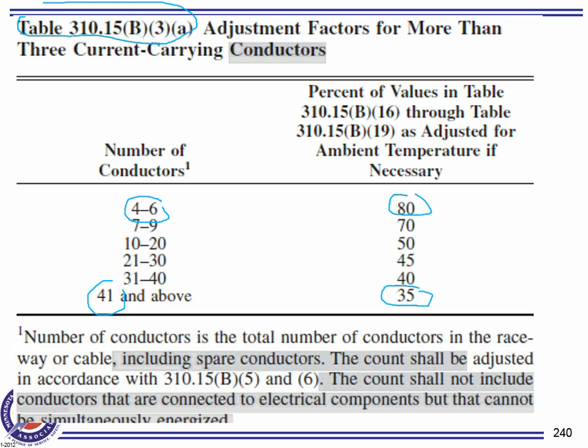So typically, guys, we rarely, if ever, go higher than that. That's kind of the industry standard. 9 hots give you 70%. Using the 90-degree column, it makes sense. In wireways, you can go up to 30 hots in the wireway without derating. But going higher than 9 hots in one conduit, you're losing 50% of your cables. It's not worth it.